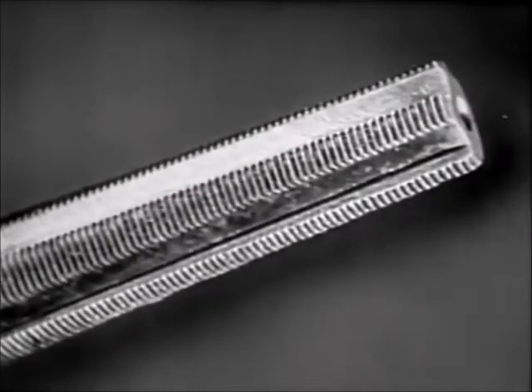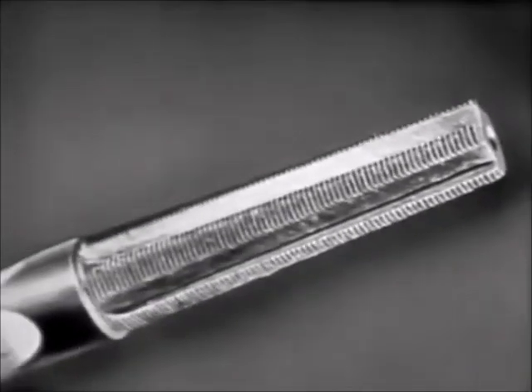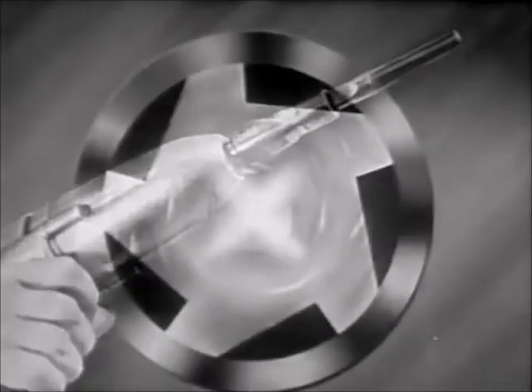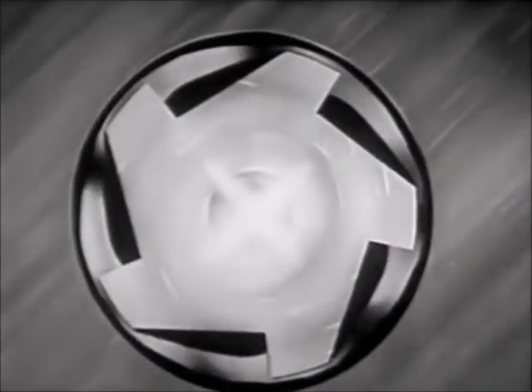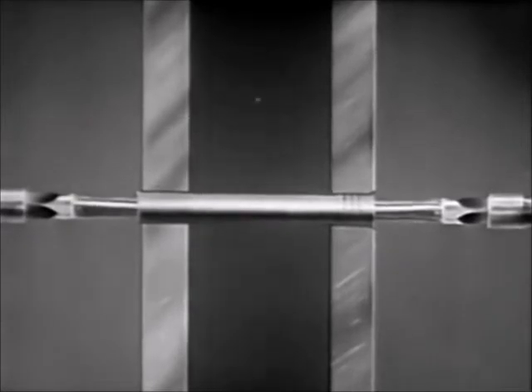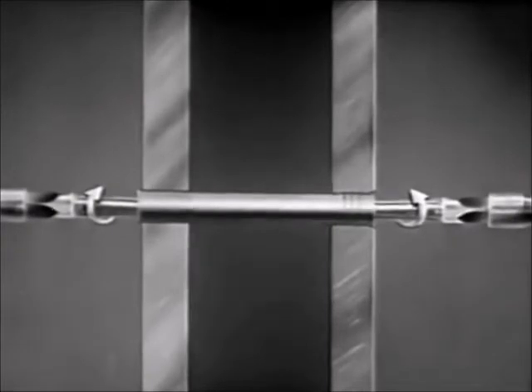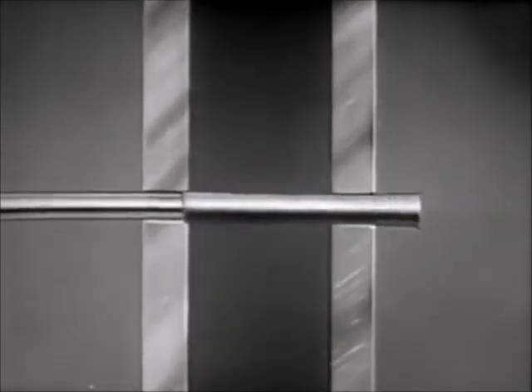This is another type of tube removal tool called a de-expander. It is driven by a rotary impact tool, either electric or pneumatic. We can show the operating principle with this cross-section of the tool. As the tool turns in the tube, cutting edges grip the tube wall and pull it in towards the center to break the expanded joint. When both tube ends are expanded, use right hand and left hand tools together so the tube will be turned in one direction. After several rotations of the tube, remove the de-expanding tools and drift the tube from either end.